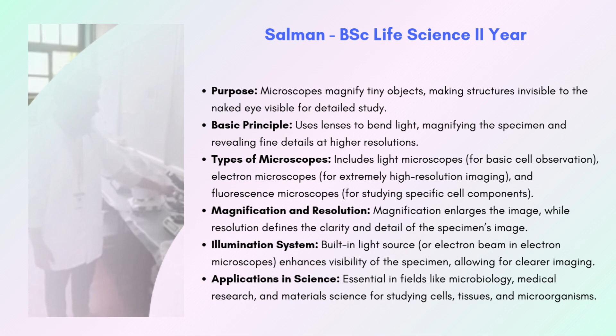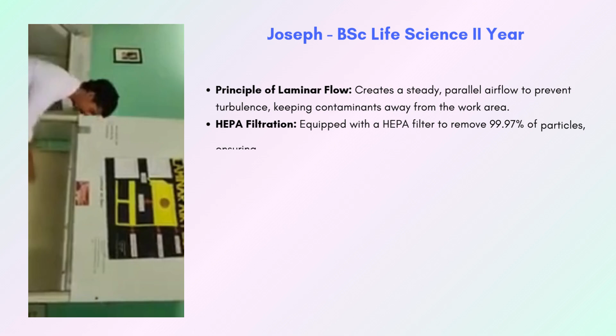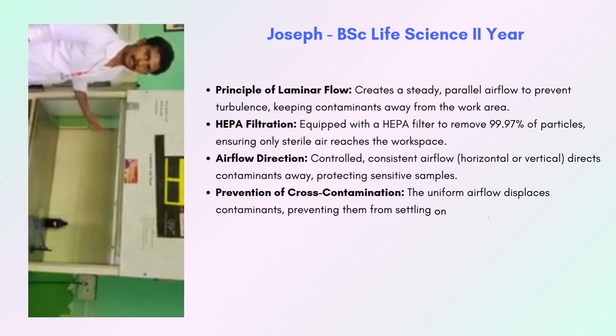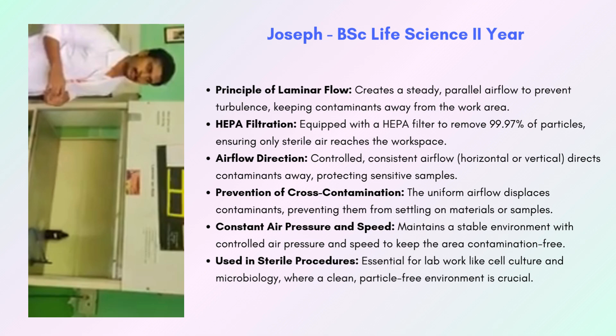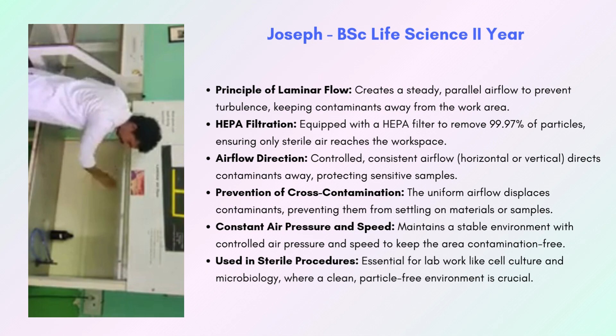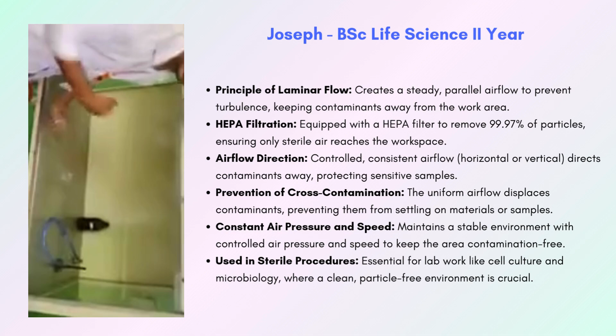And here is the laminar airflow cabinet. We use it to keep a sterile work environment inside this cabinet. There are HEPA filters, high efficiency particulate air filters, which filter out all the microbes up to 0.3 microns, and then the filtered air comes out from here and falls down to this place. Here we can keep our petri plates and culture medium, and no bacteria from outside can enter it.